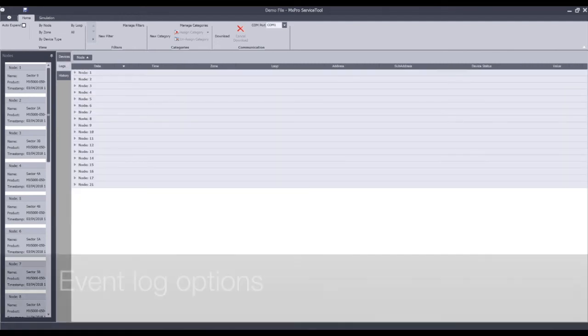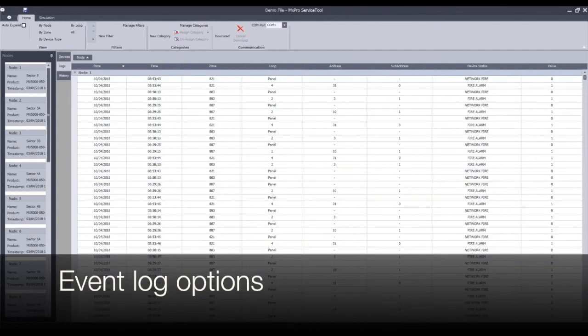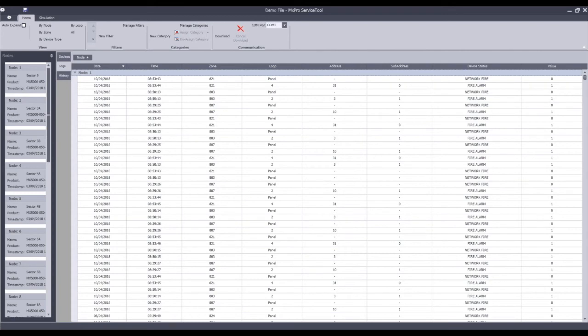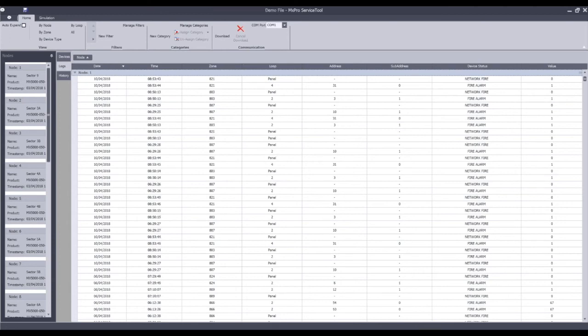Moving on to the event logs. The event log options are exactly as you would expect them to be if you were using the MX Pro local terminal software PCNet-004. This gives a chronological summary of everything that has occurred on the fire alarm system from the day it was turned on to right now. The Pro 4 series panels don't feature event logs within the service tool software — it is exclusive to the MX Pro 5s. There are 5000 events available in chronological date and time order. Once it reaches the limit of 5000 events, any new event simply bumps off the oldest event. They can be extracted through the service tool software and reviewed by scrolling through the listings.